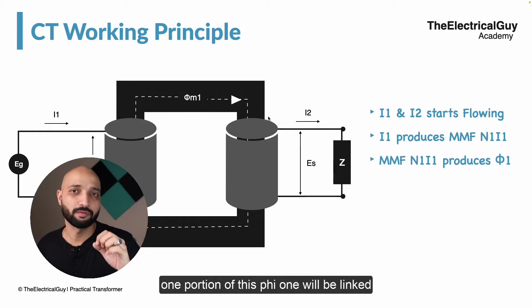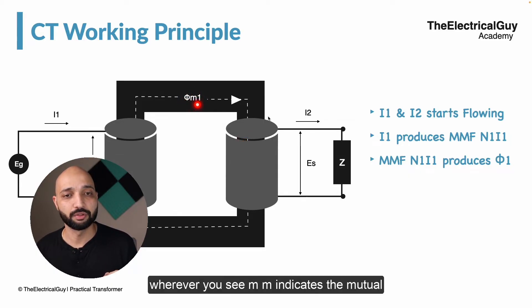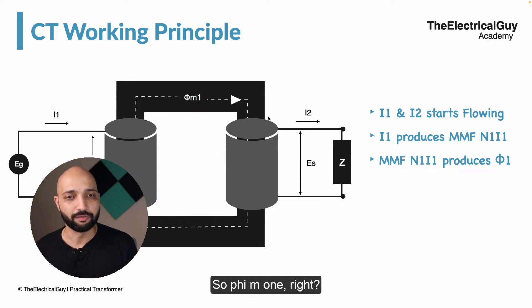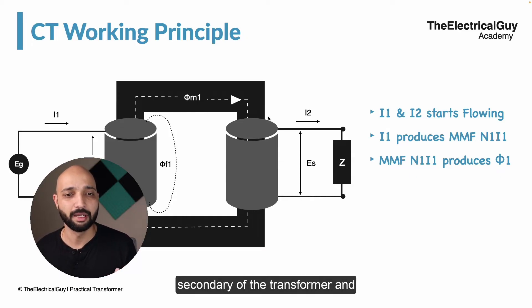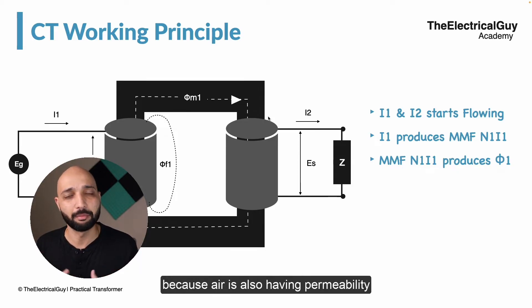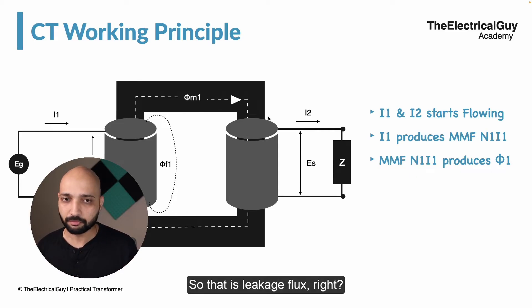This magnetomotive force will generate its own flux, which is given by phi1. One portion of phi1 will be linked with the secondary of the transformer — that is given by phiM1, where M indicates mutual inductance or mutual linking. Some part of phi1 will not link to the secondary of the transformer — that is called phiF1, which is the leakage flux. This is the flux that will link with the surrounding air, since air also has permeability. So that is leakage flux.